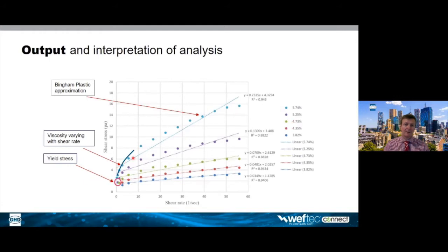And that varying viscosity is indicative of a Herschel-Bulkley type sludge, because you can see also that there is an observable yield stress, and so the power law wouldn't be appropriate, as the yield stress can be quite important in determining the system function and design requirements.